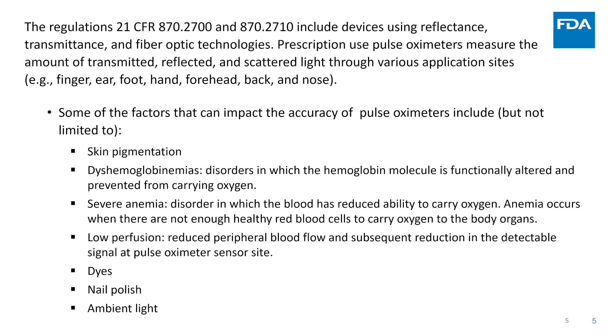For pre-market desaturation studies, as per the FDA 2013 pulse oximeter guidance, in vivo pre-market desaturation tests for SpO2 accuracy are recommended under laboratory conditions for all new pulse oximeters, as well as all previously cleared pulse oximeters that have undergone major electro-optical sensor modification and/or algorithm changes to the SpO2. In general, the purpose of in vivo pre-market desaturation studies is to verify the SpO2 accuracy of the pulse oximeter in comparison to the gold standard measurements of blood SaO2 measured by co-oximetry under a specific SaO2 range, generally 70 to 100%. Therefore, typical labeling is for general indication for non-invasive measurement of blood oxygen saturation.